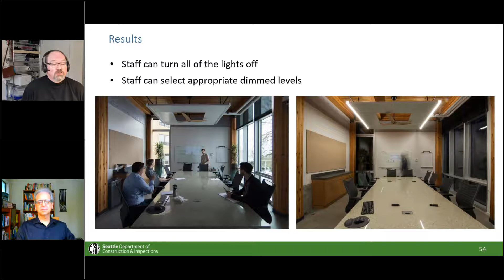The best result was that we could turn the lights off and dim according to where we wanted to — it used to be you couldn't turn the lights off at all. The key result here was that we had more than a 70% effective reduction in energy use. This was metered; the Bullitt Center is one of the most highly studied buildings on the planet, so I can tell you that the more than 70% effective reduction is well documented.